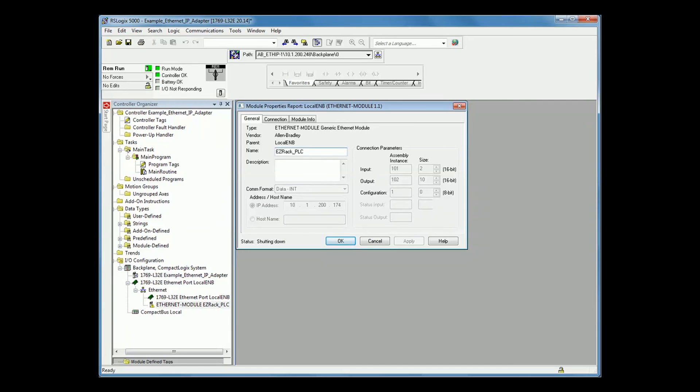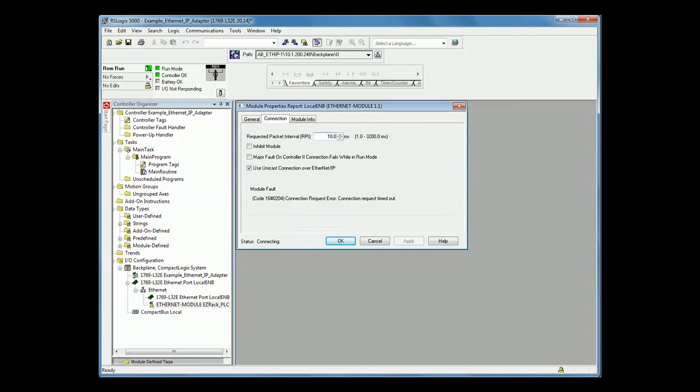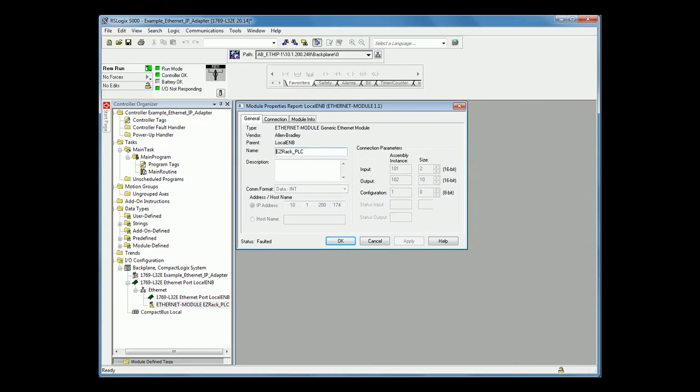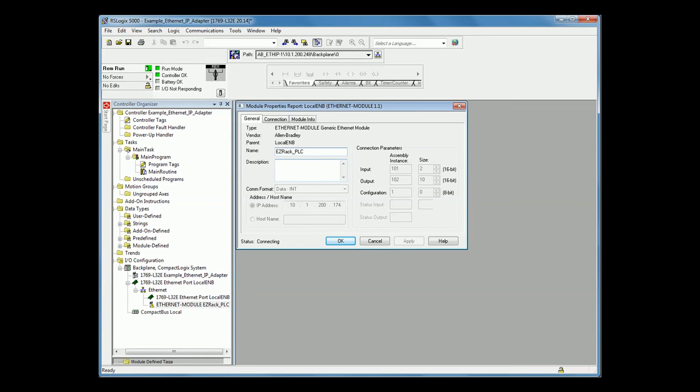The second major error that you can encounter is if your EasyRack connection request times out. This happens if you have put in the wrong IP address, if your COM format is incorrect, or if your EasyRack PLC is not connected over Ethernet. Please make sure to correct your IP address, your COM format, and make sure there is an Ethernet cord plugged into your EasyRack PLC to correct this error.